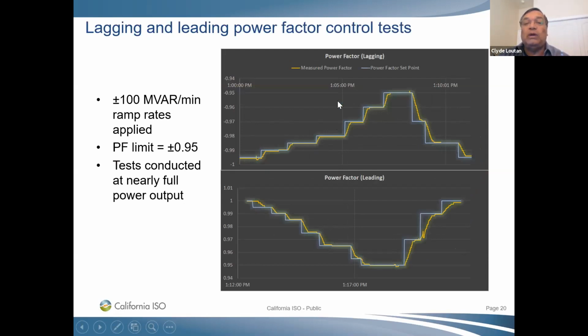This one plot here shows that at maximum output, we were able to ramp this unit up to 100 megavars. Roughly, a typical plant could produce about 1/3 of its megawatt capability in reactive, so roughly 100 megavars for a 300 megawatt unit. So both in the boosting and the bucking test, we were able to consume 100 megavars and control voltage by operating at a lagging power factor, or producing to the extent of roughly 100 megavars.